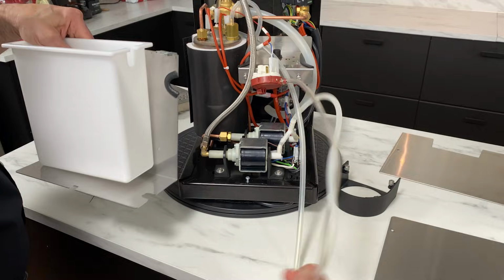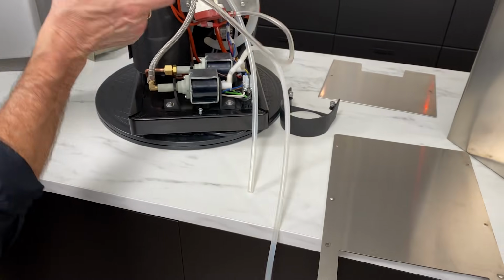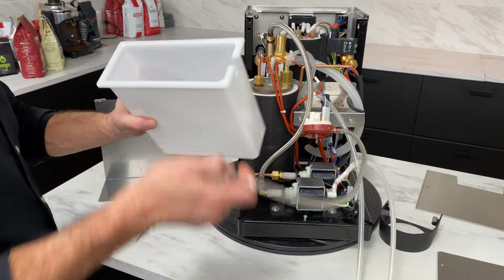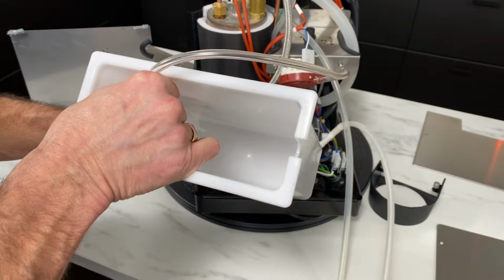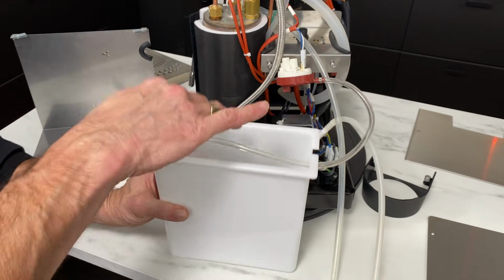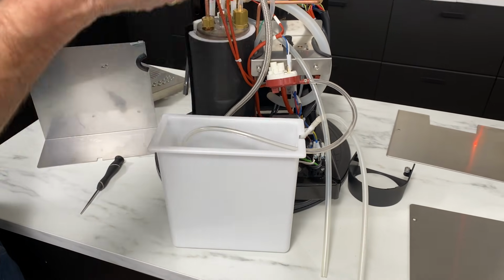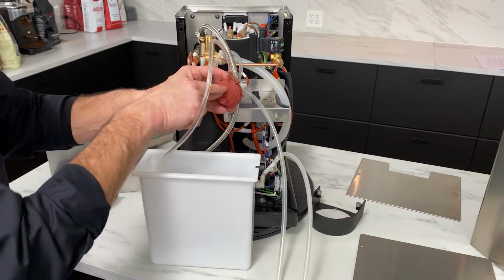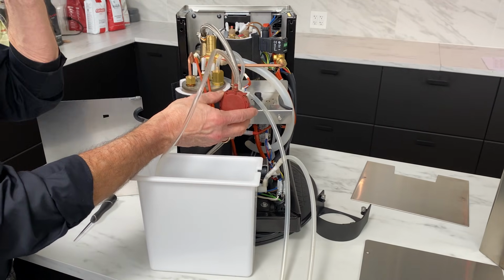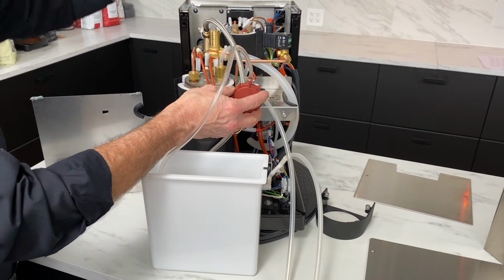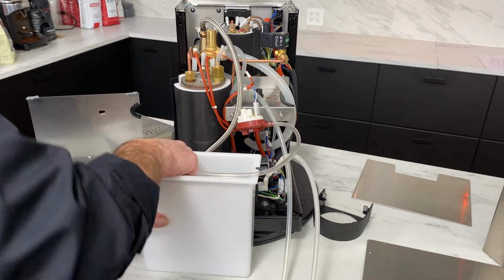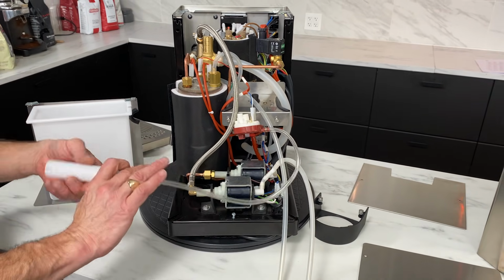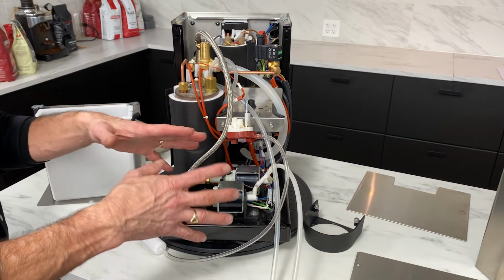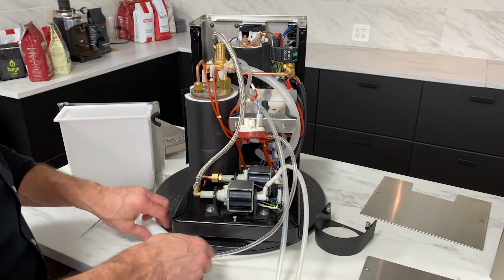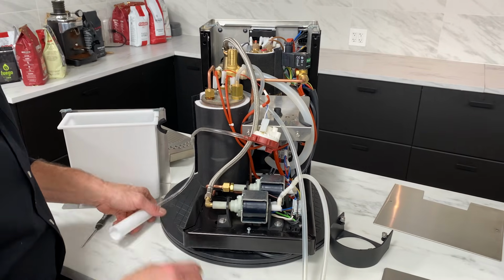So this funny looking one here, that is for sensing the water level. So that's going to sit, sorry, I'll untwist that. That's going to sit in the reservoir here. It connects down in. There's a little place where it connects in, so it'll be like that. And what it does is sense the pressure of the water in there using this sensor here, and this lets the machine know if it's out of water. You'll get a message in the display up front that it's out of water. So that's that one. It's a unique system. A lot of machines will use conductivity of the water and probes or weight or something, and this is going to use the air pressure through this.